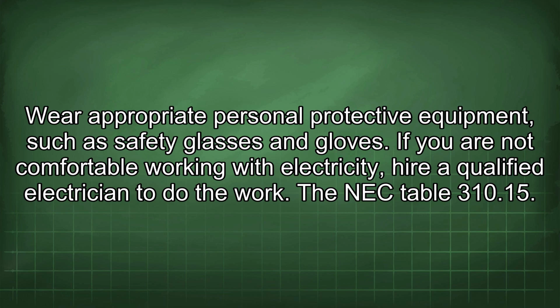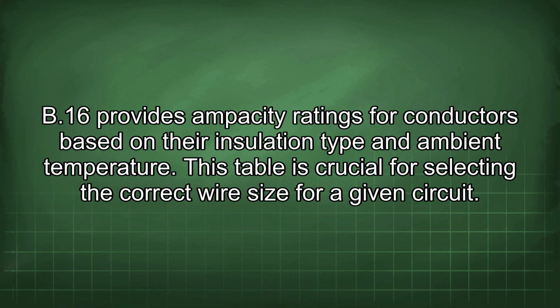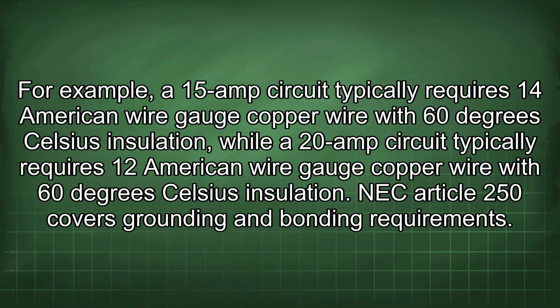NEC Table 310.15(B)(16) provides ampacity ratings for conductors based on their insulation type and ambient temperature. This table is crucial for selecting the correct wire size for a given circuit. For example, a 15 amp circuit typically requires 14 American wire gauge copper wire with 60 degrees Celsius insulation, while a 20 amp circuit typically requires 12 American wire gauge copper wire with 60 degrees Celsius insulation.